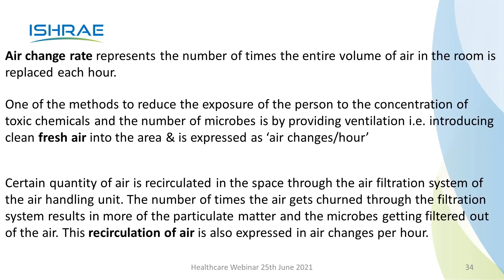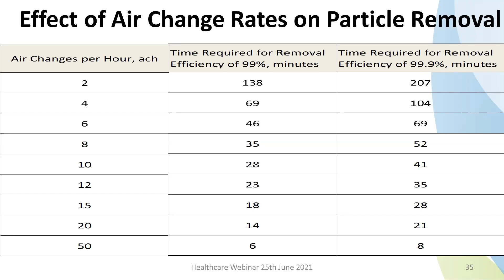So you've got this particular thing, the effect of air change rates on particulate removal. On the left side, we have 2 air changes per hour, right up to 50 air changes per hour. Time required for removal efficiency of 99% in minutes: if it is 2 air changes, it takes 138 minutes. 12 air changes, it is 23 minutes. 50 air changes, it is 6 minutes. The rightmost column says the time required for 99.9% efficiency of removal. So it takes a lot more time for that kind of efficiency.